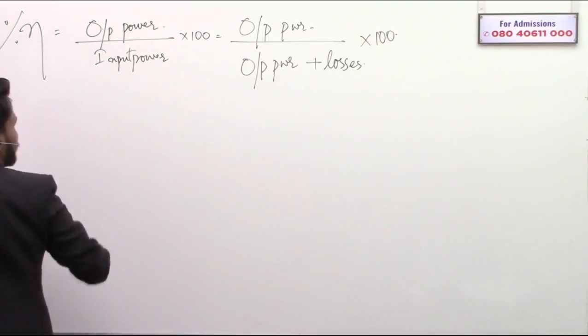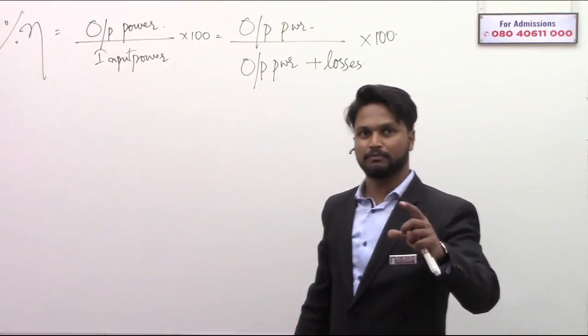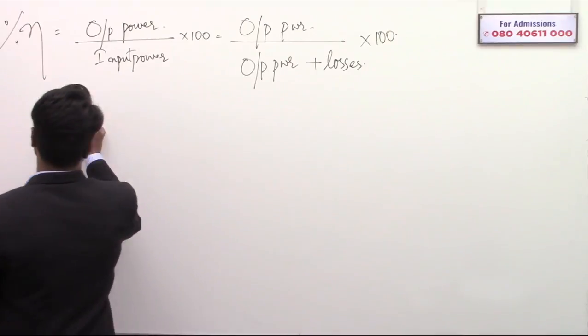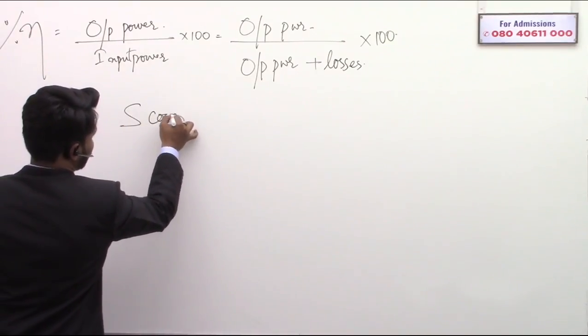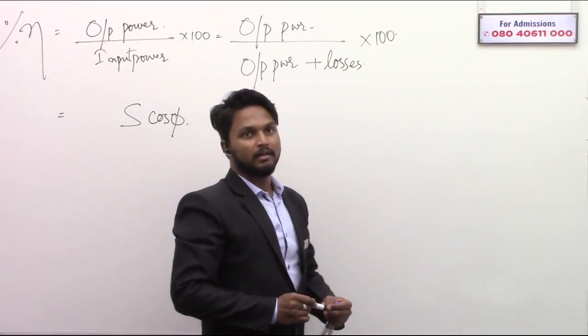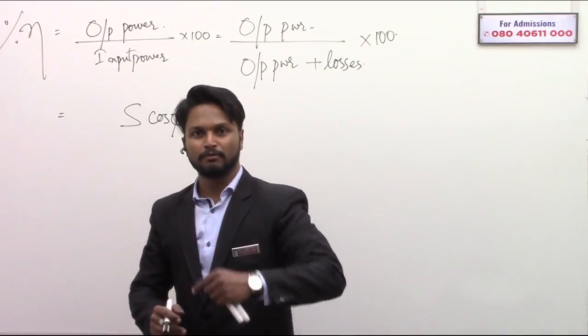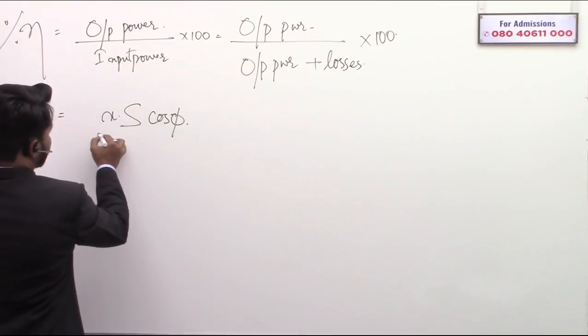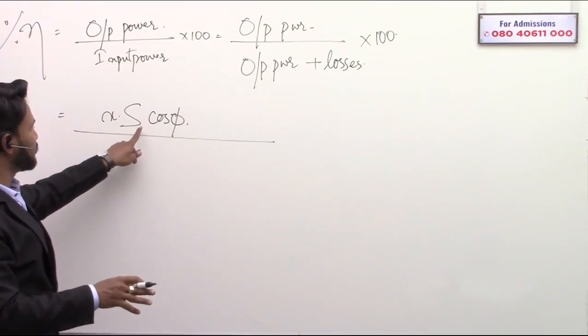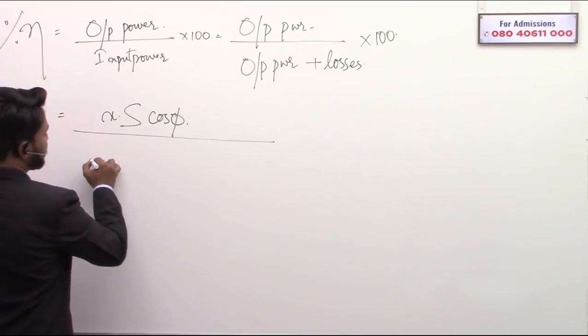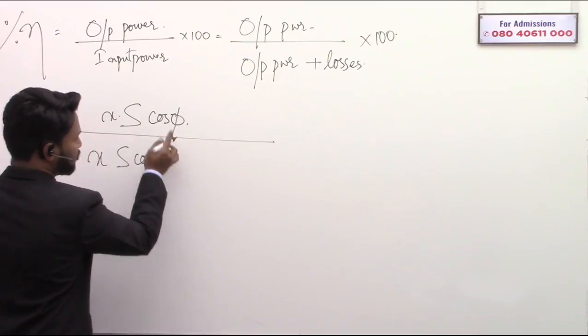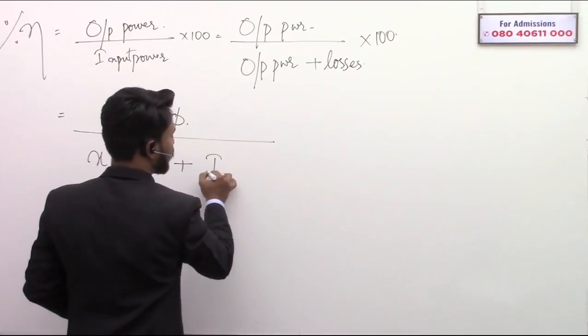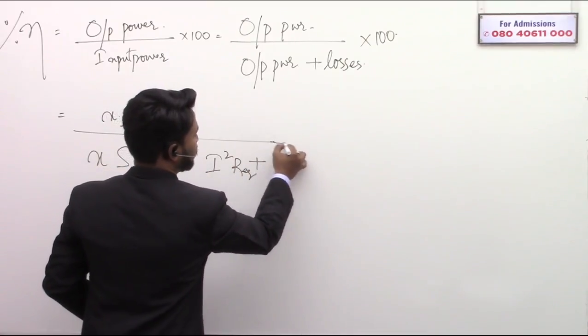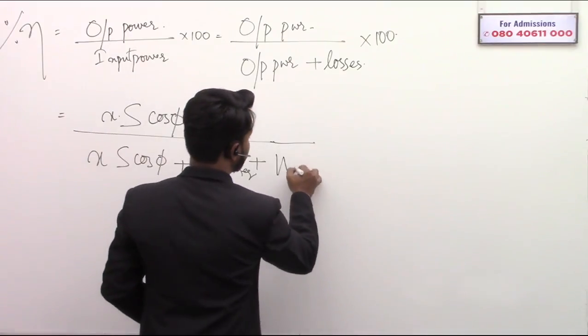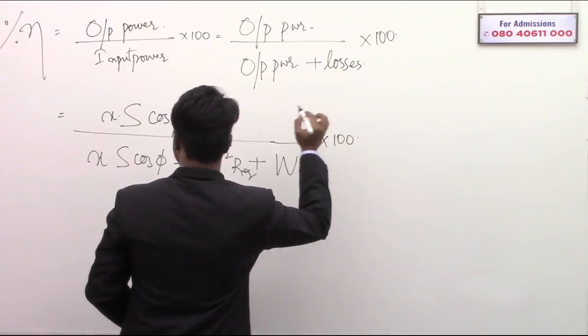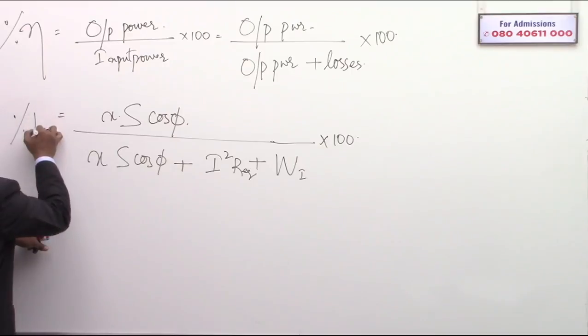So what is output power? The rating of the transformer is given. Let us say S is the rating of the transformer. Then output power will be equal to S cos phi. So the output at an xth fraction of load is x multiplied by S cos phi, where x is the fraction of load. Again, this is divided by x S cos phi plus losses, output upon output plus losses. What are the losses? Copper losses, I square R equivalent, plus iron losses, let us call it Wi. This multiplied by 100 is the formula to find the efficiency at any particular load.